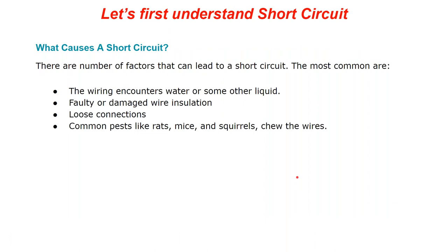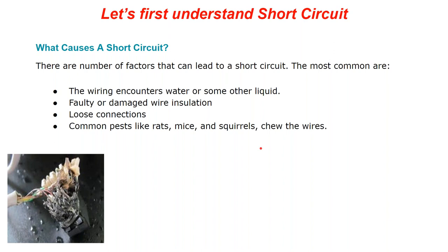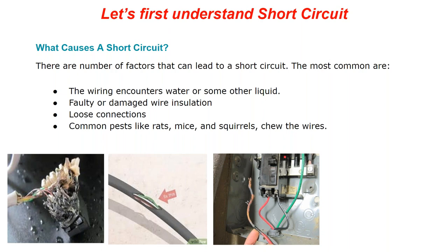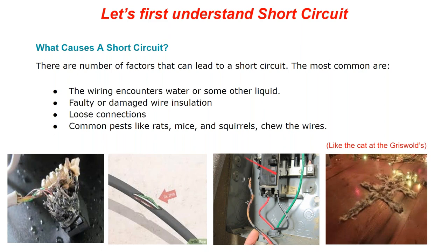What causes a short circuit? Several factors: water damage — that's why NEMA ratings matter for damp or outdoor environments. Cables that get pinched or damaged can also cause a short circuit, as can a loose connection or loose termination. And sometimes animals can get into outdoor panels and chew through wiring, causing a short circuit. We have to safeguard against all of these.